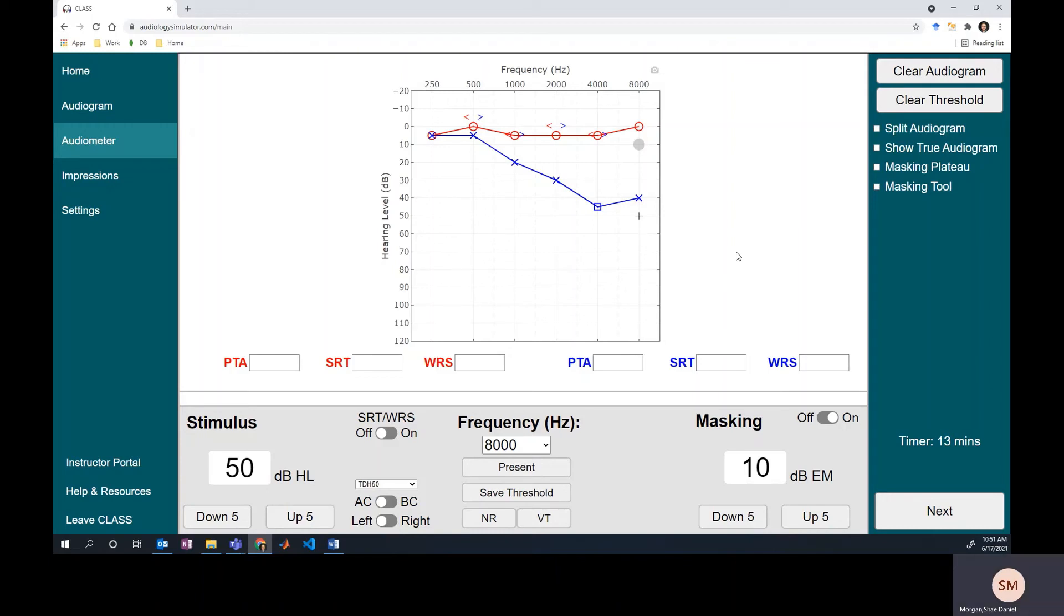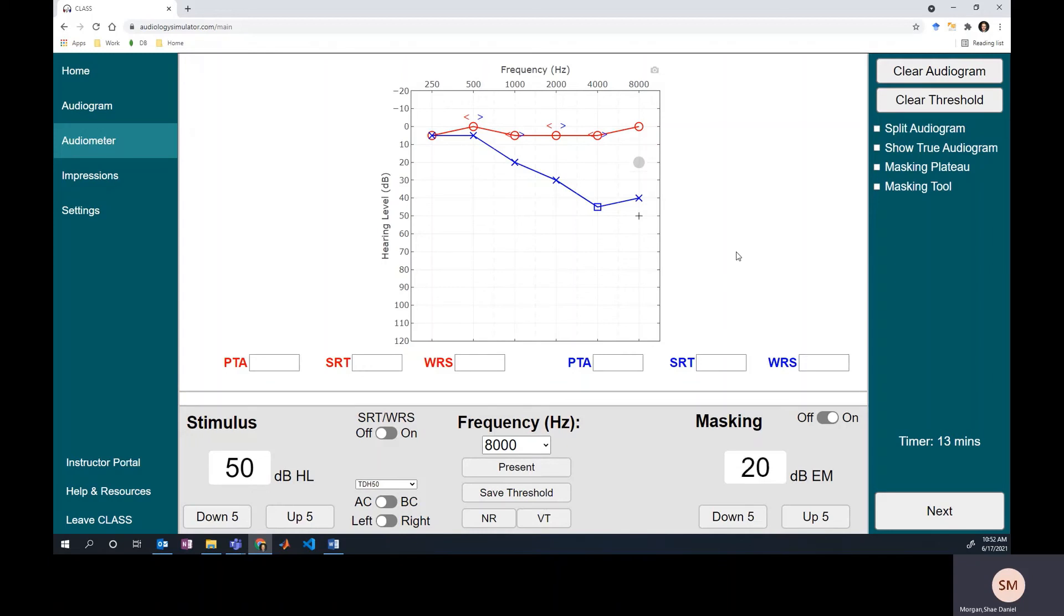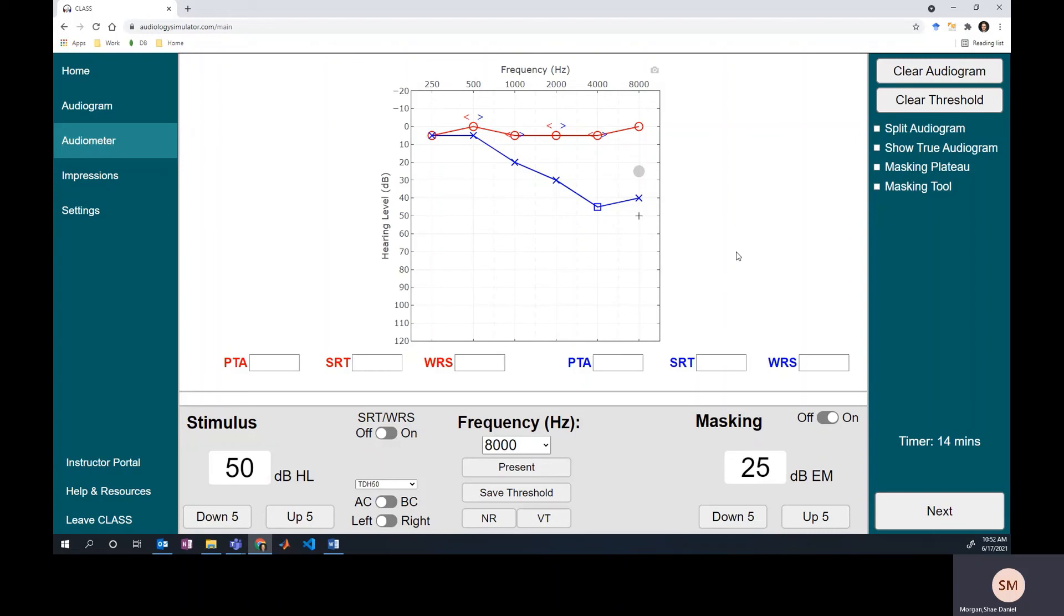So we need to increase the level of our masker again to make sure that this response is truly coming from the left ear and not the right. We'll go up one time, they respond two times, we still get a response three times, and we still get a response. Sometimes people recommend four times or four masker increases just to be sure. This is what people are talking about when they say they want a 15 to 20 dB plateau before saving the threshold. They want you to raise the masker levels three to four times to make sure that there's no way the response is coming from the non-test ear.